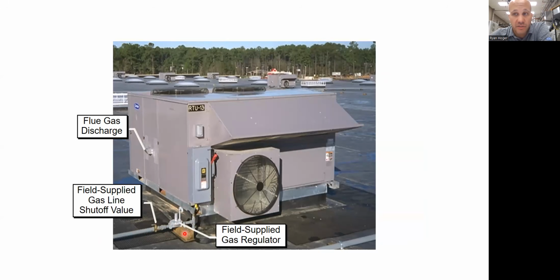If there is no gas line to it, you definitely don't have a gas-fired rooftop. You probably have an electric resistance version, or it could be one with no heating. That's not common where we live. Or it could be one that's a heat pump, also not currently common. But there'll be a gas line to it, a gas regulator, and then there'll be a flue.